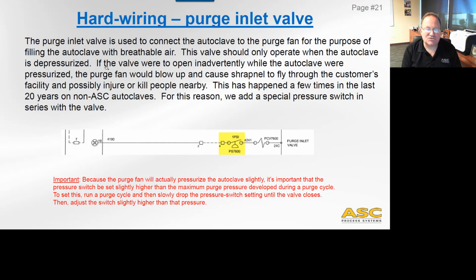For this reason, we have added a special pressure switch that's put in series with that valve, a dedicated switch, and we call it a 1 PSI switch, but actually that pressure that gets set is unique to each purge system. Because the purge fan will actually pressurize the autoclave slightly when it operates, it's important that the pressure switch be set slightly higher than the maximum purge pressure developed during that purge cycle. So to set this, you run a purge cycle and then slowly drop the pressure switch setting, adjust it down until the valve closes, and then adjust it up a little bit so that the valve opens, and that'll be the correct setting. So you want to be just above the normal purge pressure, which is going to be developed when that purge fan is operating.